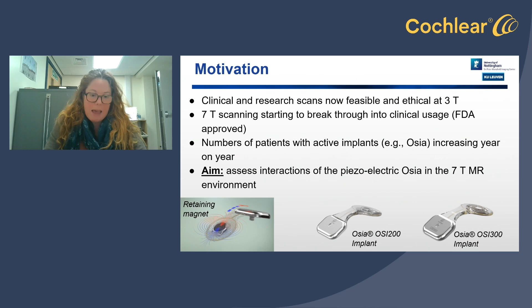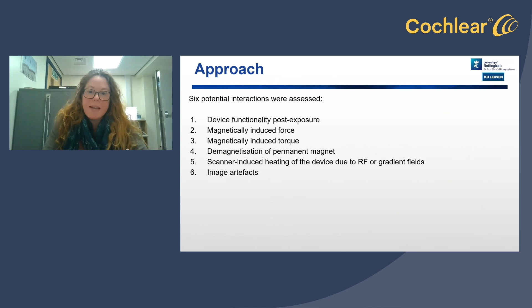So that, alongside the year-on-year increase in implant users, has prompted us to assess the interactions between the Osia and the 7T MR environment. We've assessed device functionality post-exposure to the MR environment, magnetically induced force and torque experienced by the implant in the scanner, changes to the magnetization of the implant's retaining magnet following exposure, scanner-induced heating of the device separately due to both RF and gradient fields, and image artifacts resulting from the presence of the implant. All tests were designed to align with the relevant industry standards and recommended procedures.